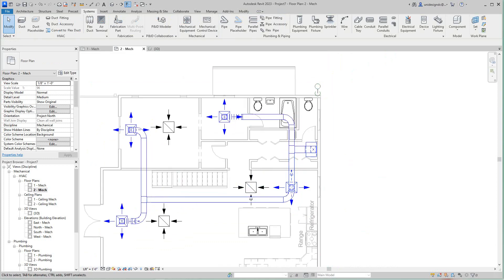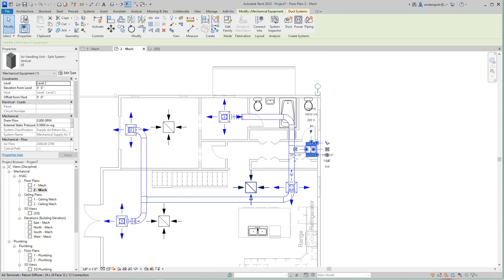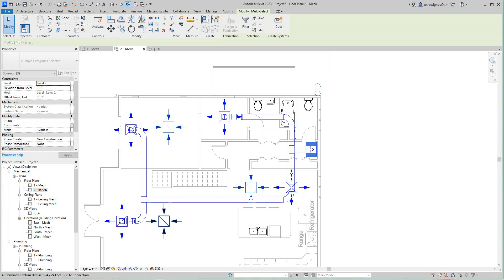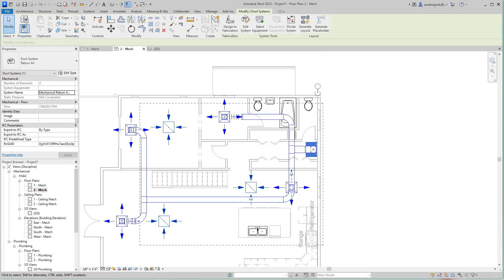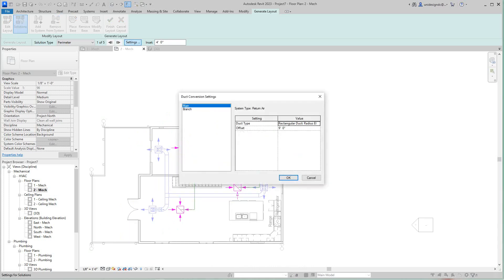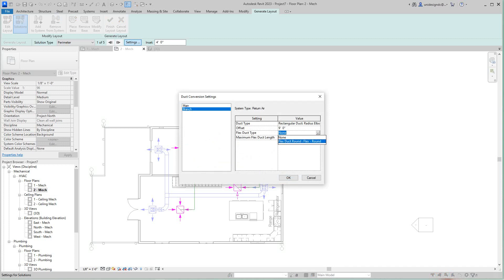With the return terminals placed, we do the same process as before — hit Ctrl and select each return terminal, then hit Ductwork. This time we choose Return Air and click OK. Then we click Generate Layout. In Settings I'll push the offset up to 10 feet 6 inches. For the Branch I'll leave it at 6 feet, set flex duct to round, and click OK.